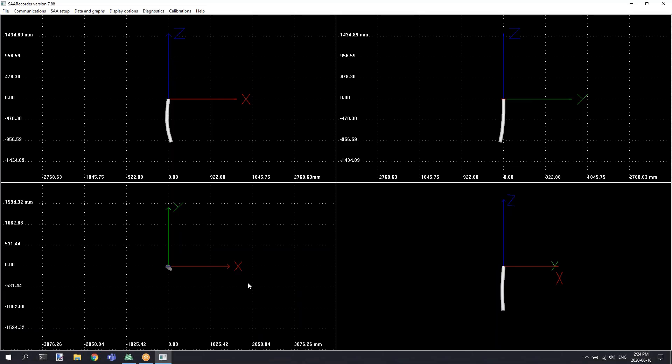As well as recording raw data readings, the SAA recorder tool is also used during the installation of vertical SAAVs. During the installation, an SAAV needs to be pumped to ensure that there's proper compression in the instrument before the installation is capped off and completed. This ensures that the shape array retains its proper cylindrical shape within the conduit.